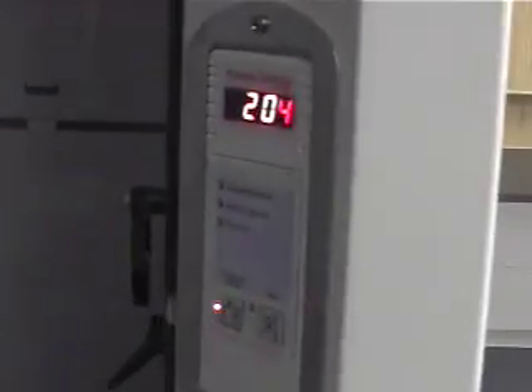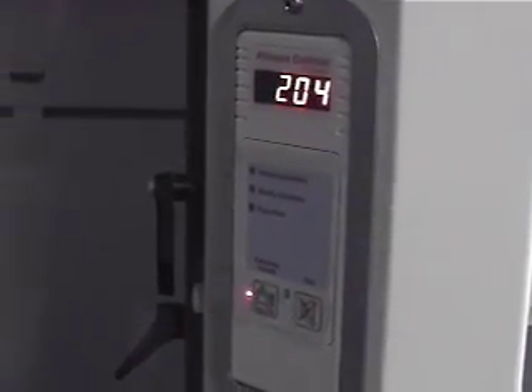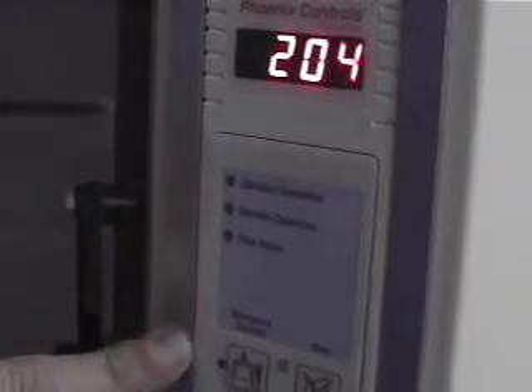So 100 feet per minute has been found to be the best number for having somebody here working and having all the fumes and everything go through the hood. If you get up too high, you can create little turbulent eddies and some can creep back out. So emergency exhaust is just when, okay, I've got to get as much stuff out of there as I can from inside there, and you just push emergency exhaust. You don't really need that normally. I've never seen anyone actually need it or use it, but it is there just to be there. If it's in alarm, there's a mute button so you can make it stop beeping at you. That's really all there is to the buttons as far as function. Obviously you can see that standard operation light went away. So it's no longer in standard operation. Somebody's got it in emergency mode.